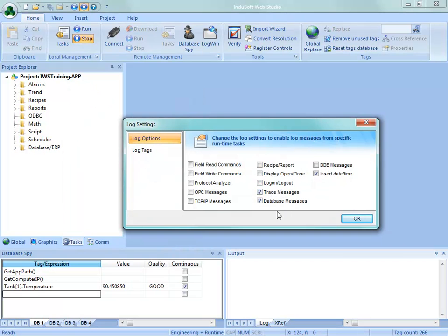Some other things that you can do is include trace messages. Trace messages are a function that you can put anywhere in your scripting language. You can even put them with the $sign in front, the trace function, into a VB script. So if you're not sure if your logic is jumping you to the right place within a script, you can put a message, I am here now, or I'm at step number 1, now I'm at step number 2, and have that come out in the output window and see where you're at, kind of help you troubleshoot where you're at in script.